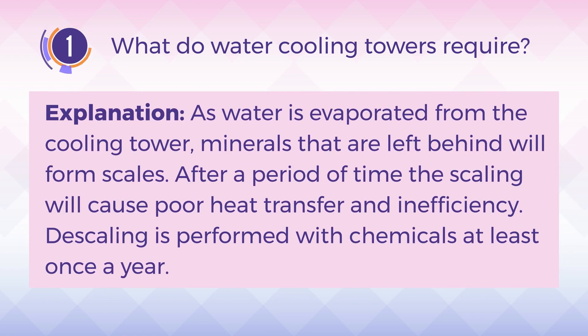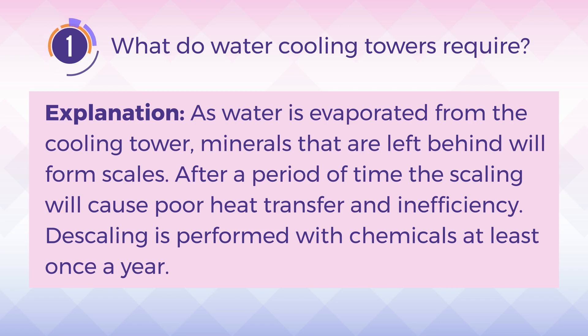The correct answer is D, periodic descaling. As water is evaporated from the cooling tower, minerals that are left behind will form scales. After a period of time, the scaling will cause poor heat transfer and inefficiency. Descaling is performed with chemicals at least once a year.